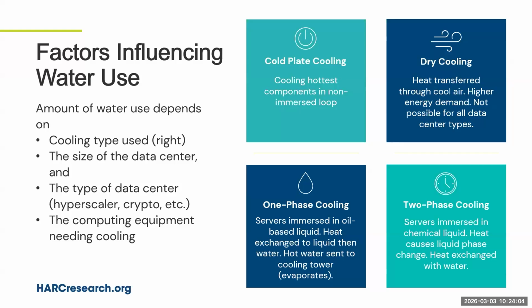On the right I show some example cooling technologies used in data centers. Cold plate cooling, which cools the hottest components through a cold plate attached to the computing equipment. One-phase cooling, which uses an oil-based liquid to cool the equipment, where heat is transferred from that oil-based liquid to a device that removes the heat from that loop into the atmosphere—the same happens in the cold plate cooling system.